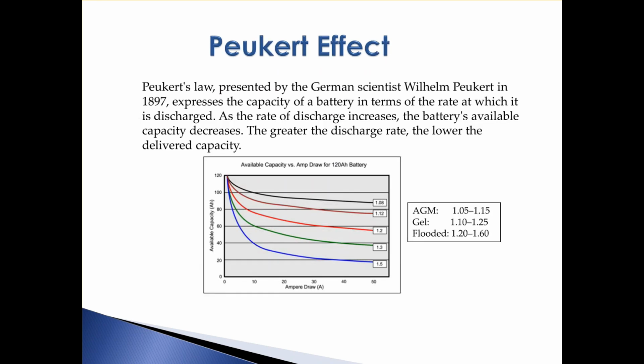Peukert's effect, or Peukert's law, was found by a German scientist back in 1897, not long after lead acid batteries were invented — this is the same technology still in use today. A battery's capacity is rated in amp hours, but the available capacity changes drastically based on the ampere draw. This battery is rated 120 amp hours, and at low current you would get 120 amp hours out of it, but the current draw would have to be very low, only an amp or two, to achieve that.